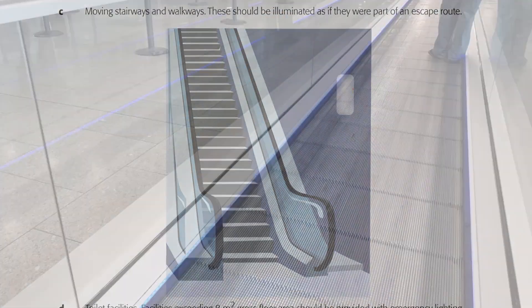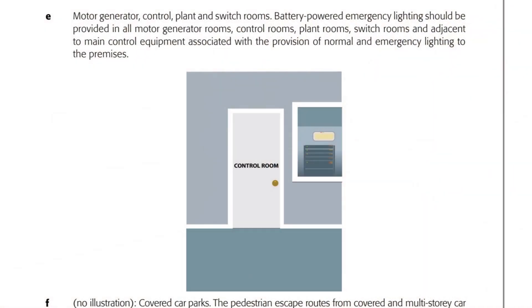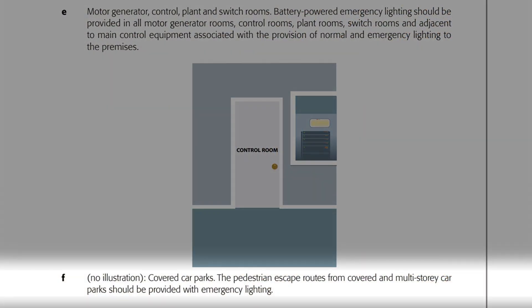Emergency lighting is also required on escalators and moving walkways, in toilets with gross floor areas over eight metres squared, and the guide specifies that battery-powered emergency lighting should be provided in all motor generator rooms, control rooms, plant rooms, switch rooms, and adjacent to main control equipment associated with normal and emergency lighting. It makes the point these should be battery-powered — not supplied by a backup generator — since if a generator failed, it would also cut the lights in the room the generator was in. Finally, pedestrian escape routes from covered and multi-storey car parks should also be provided with emergency lighting.